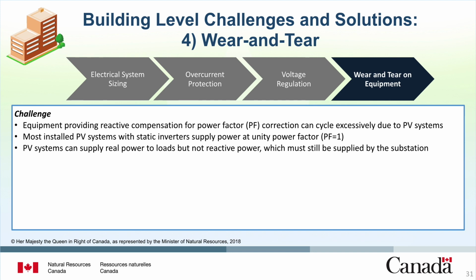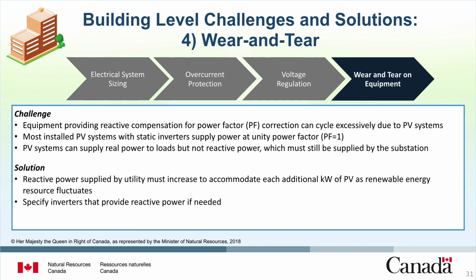supplied by the substation. To manage this challenge, the reactive power supplied by the utility must increase to accommodate each additional kilowatt of PV as it varies widely and suddenly as the renewable energy resource changes. Another solution is to specify inverters that provide reactive power if needed. This concludes our discussions of challenges and solutions for integrating renewable systems at the building level. Next, we will look at how substations manage integrating renewable energy.